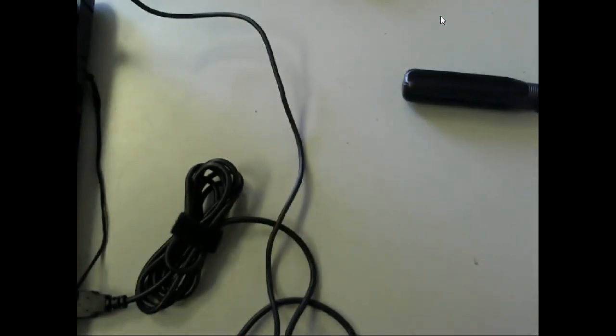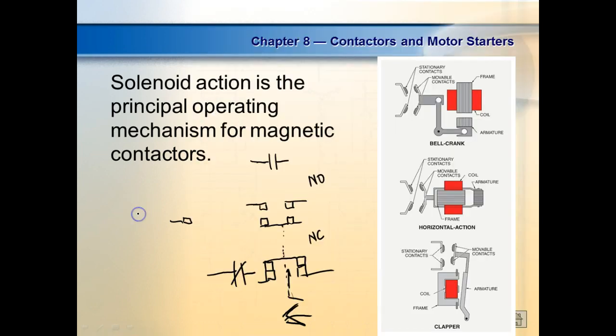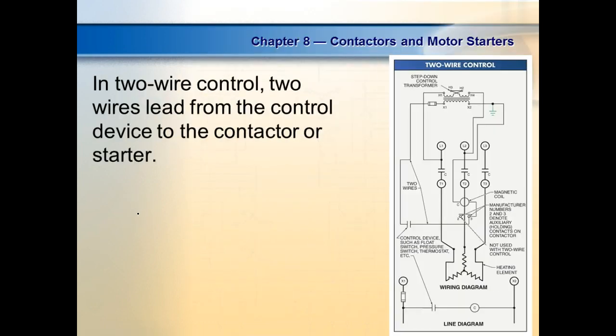And this is the control relay. I think I showed y'all that control relay. It's got like 8 contacts on it, right? Some of them can have a lot of contacts. This is a wire diagram. By the way, this is called a two-wire control. So if we count the one between L1 and the load, then this right here would count as one, and that would count as two. So some people refer to this as a two-wire control. Everybody okay? So these would get two different wire numbers, right? You understand?